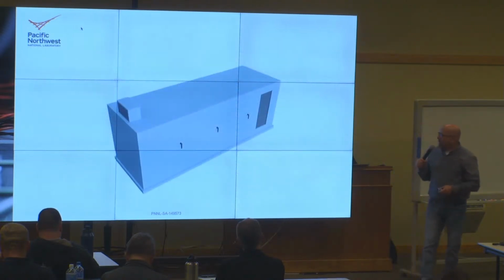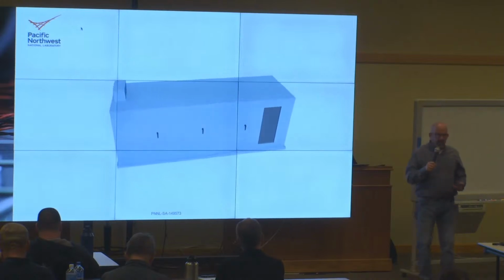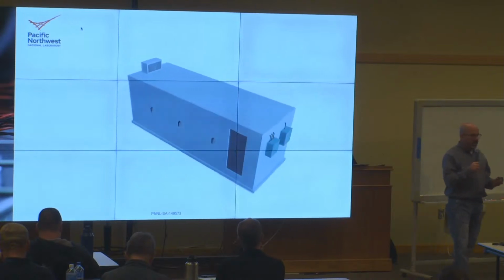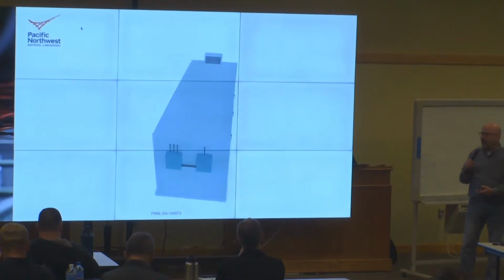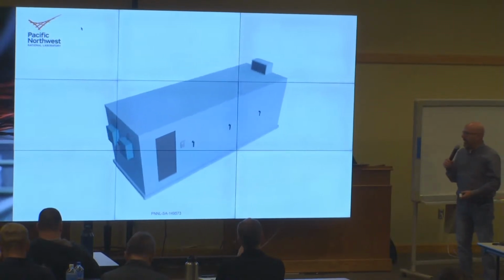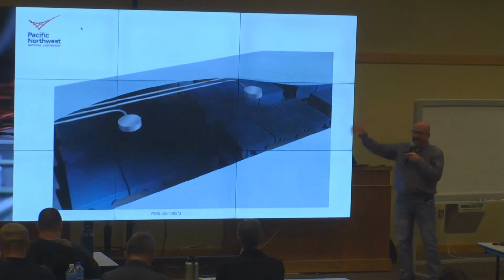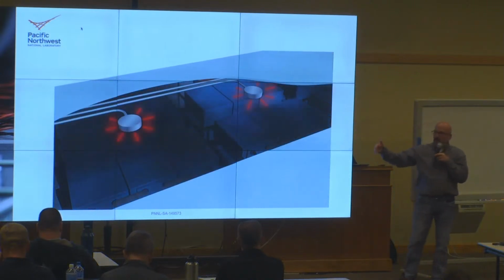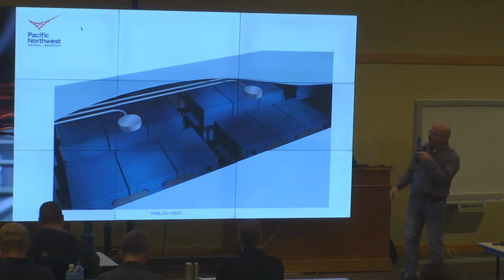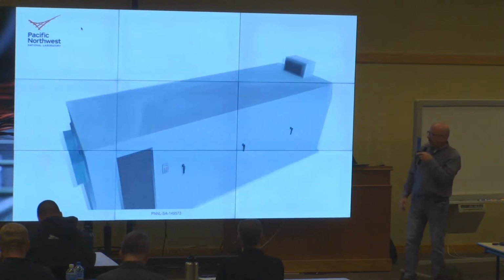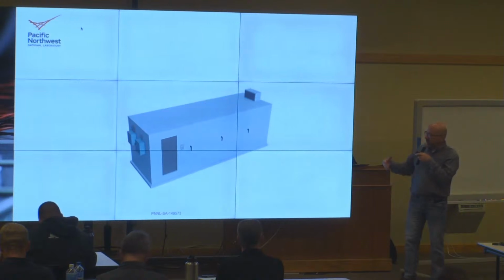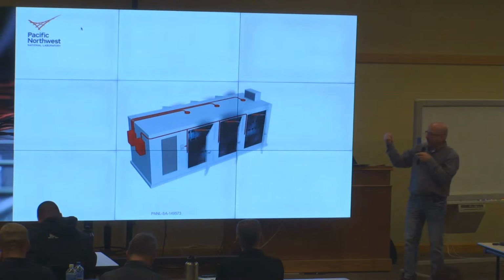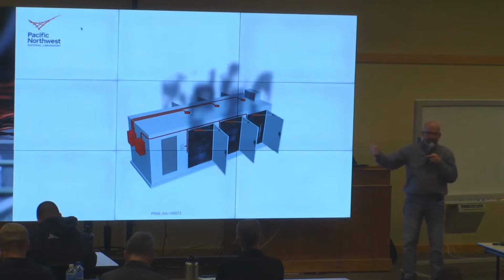So we said, okay, if these cabinets have doors, why can't we use the doors to exhaust? This is a generic enclosure that's having some kind of failure inside. The detectors that would already be installed inside it, whether gas, smoke or heat, are monitored by the system. That's a requirement of 9540. The system that we call IntelliVent would take that signal from the fire alarm panel and, utilizing UL listed access control devices, open the doors at a very early stage.